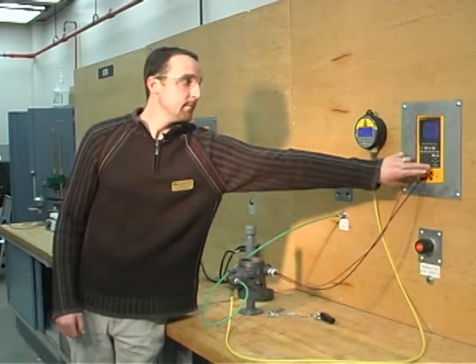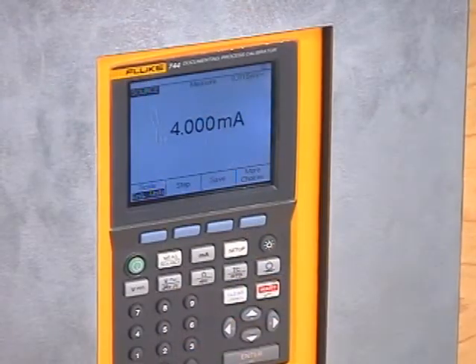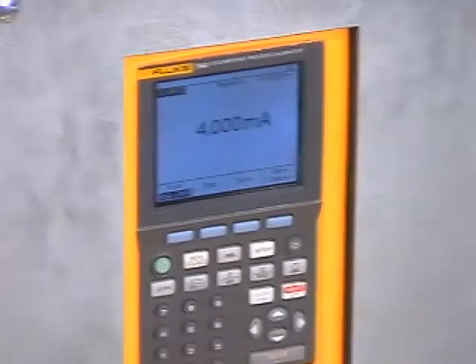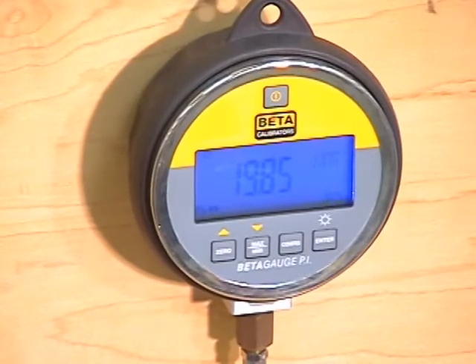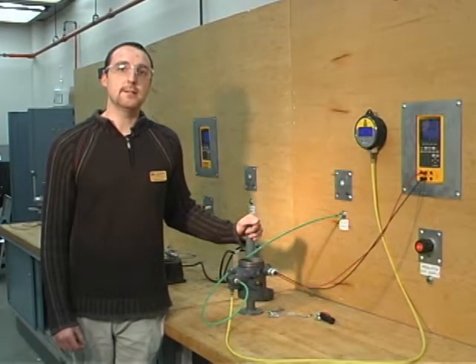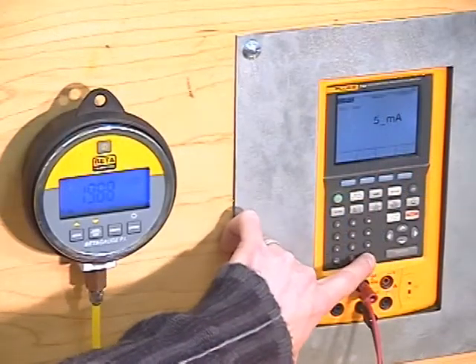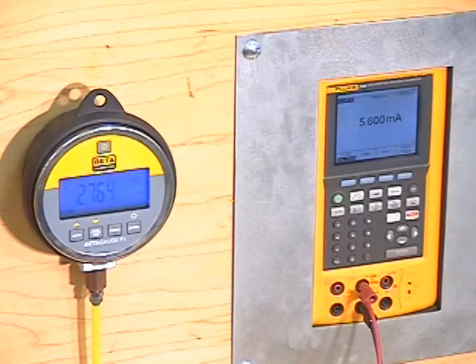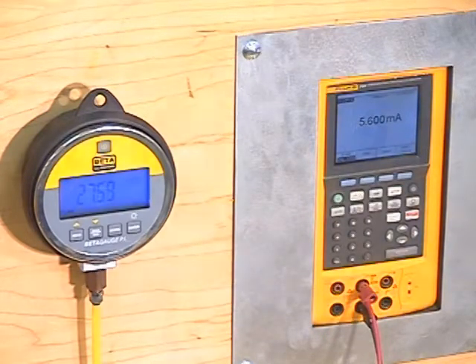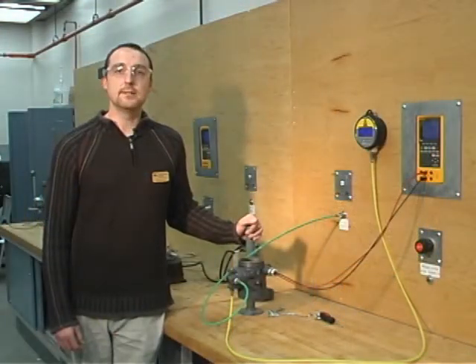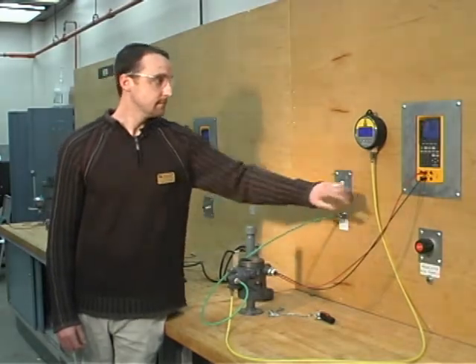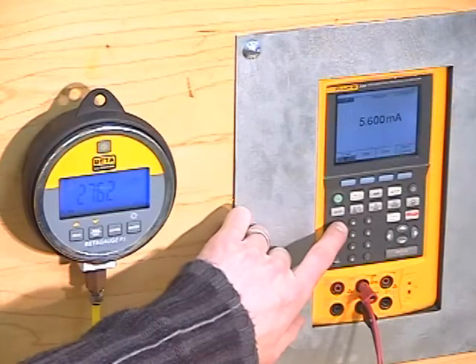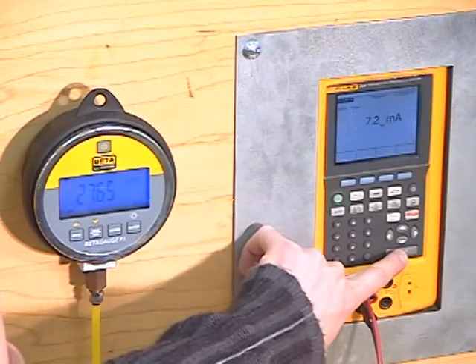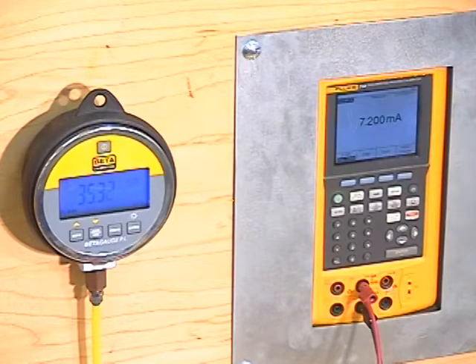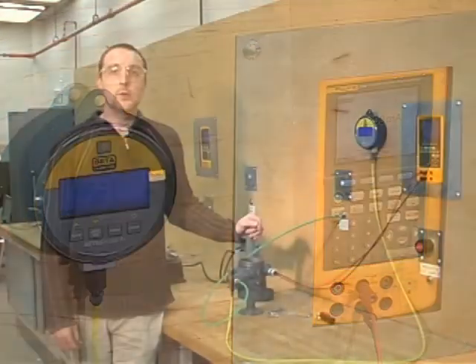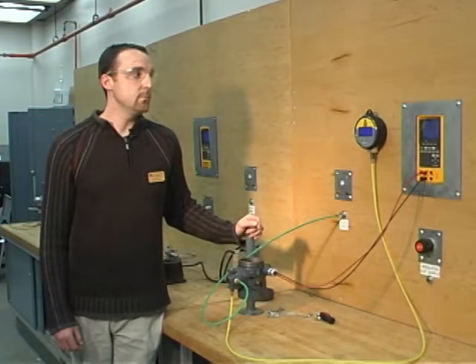Now, at 4 milliamps, note that our output pressure is about 19.85 kilopascals. Next, for our 10% increment, we will be going to 5.6 milliamps. At 5.6 milliamps, we are at 27.6 kilopascals. Next, we will do 7.2 milliamps, and we are rendering 35.31 kilopascals.